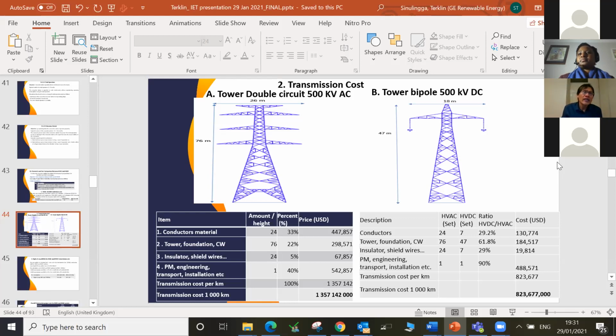The same for AC substations, which are quite mature technology. So the comparison will not be apples to apples because the components are not the same. For VSC, we are talking mainly about the converter valve, converter transformer, and DC equipment. But AC is different from a DC substation. This is what I want to tell here. So the component costs are different, but on average, AC and DC have about the same, not so high operation cost per year. Thank you.